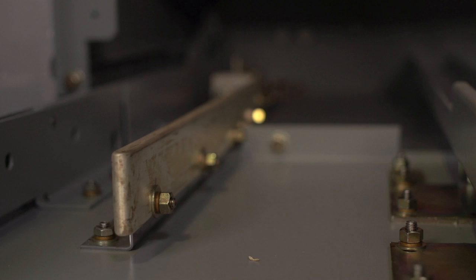When working around medium voltage equipment, it's critical that metal structures are grounded. On the left side of this cell is a ground bar. The bottom of the circuit breaker has a contact shoe that contacts with the ground as soon as you insert the circuit breaker into the cell.